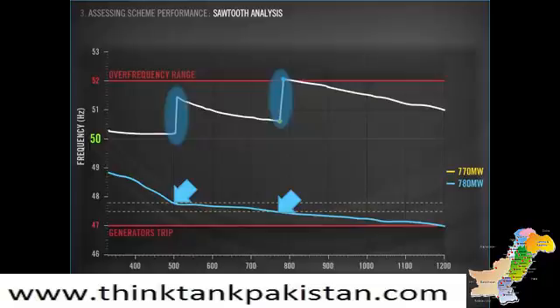Viewing the events in this way allows us to focus on areas of concern. In this example, an event of around 800 megawatts is going to result in overshoot above the 52 Hz limit. A larger trip size of 1200 megawatts results in the frequency going below 47 Hz. Both of these scenarios result in non-performance, which we want to avoid. The sawtooth is a huge leap forward for our analysis and gives a much better picture of how the scheme performs across different event sizes.